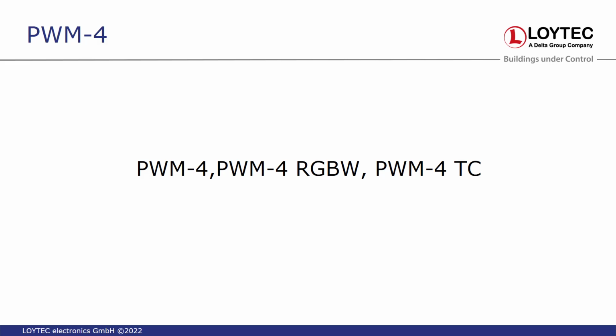Sure. This is why you have the different models. I mean, you have the wrong model. Yeah, but it works. We made one installation, and it works really fine. But therefore we have the other ones. With the other ones, you will only see one DALI address, and then you have the right DALI commands, of course. That's why we have the different models. It's basically the same hardware, like you say, but the firmware is different, so it behaves differently on the DALI channel.